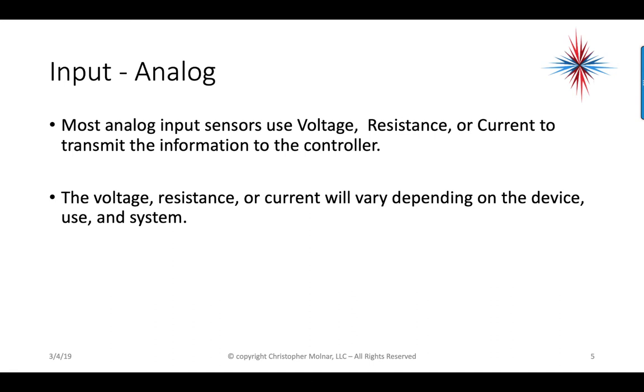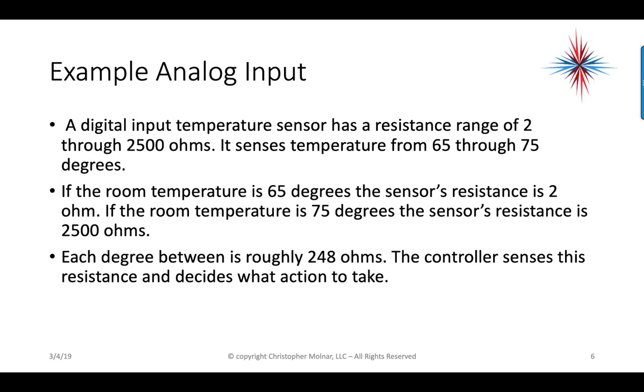The voltage, resistance, or current will vary depending on the device, the use, and the system. A basic example of an analog input would be a temperature sensor with a resistance of 2 through 2,500 ohms that senses temperatures from 65 through 75 degrees. If the room temperature is 65 degrees, the sensor's resistance is 2 ohms. If the room temperature is 75 degrees, the sensor's resistance is 2,500 ohms. Each degree between these two min and max temperatures is roughly 248 ohms. The controller senses this resistance and decides what action to take — we're dealing with ranges of values.